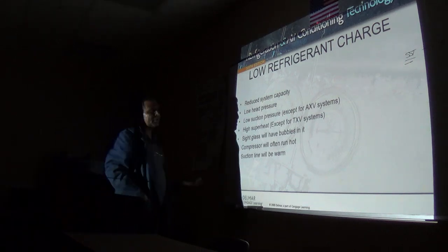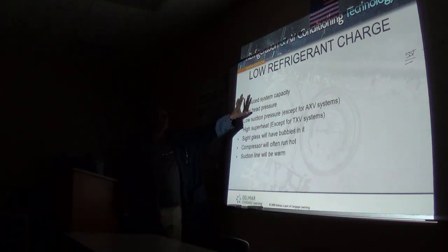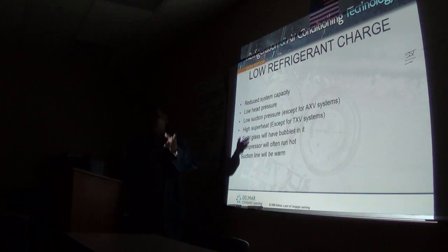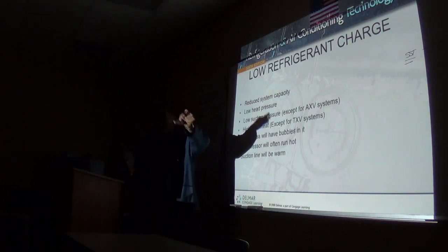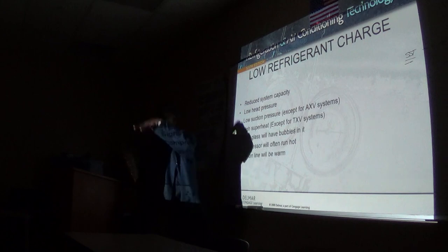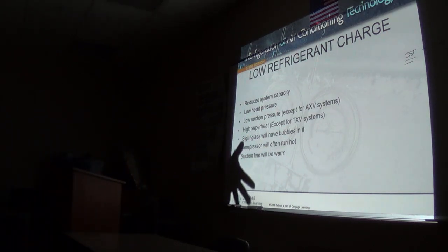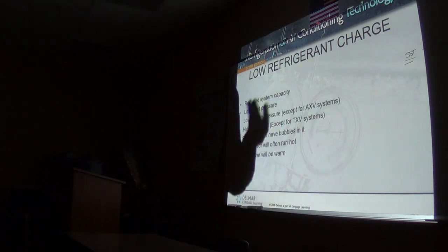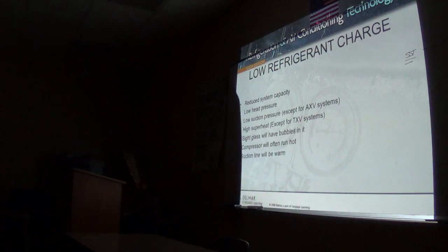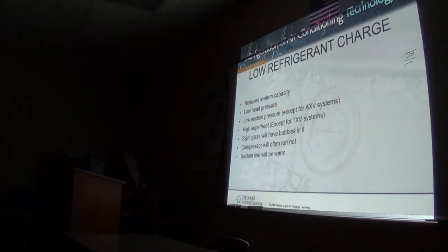Yeah, but chances are in this case, once you have overall low pressures, low head pressure, low suction pressure, you're looking at an undercharged system. And chances are it lost the gas either through a leak, or somebody accidentally did something and played with a service valve pin, or the service valve pin probably developed a leak, which they always do at times.